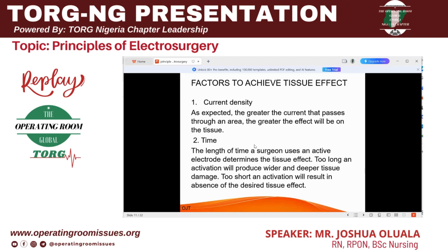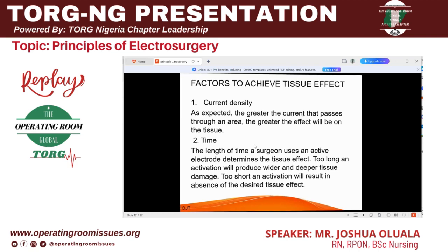It's not seeing the effect he actually wanted to see on the tissue. But as time goes on, we all get on the same page. So the timing is very, very important. When you put it, of course, you must allow a desired time for you to have the desired effect. Too short an activation will result in absence of the desired tissue effect. Once you put it, for example, in monopolar, you just press on the cord without going through the length of the desired length you actually want to cut. You are not going to achieve it. Or when you are coagulating, the same thing also happens.